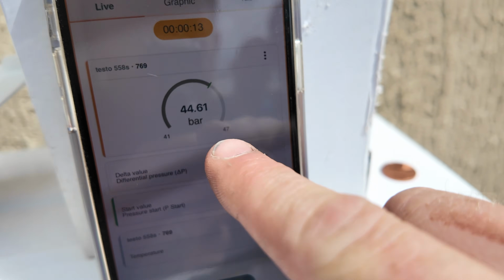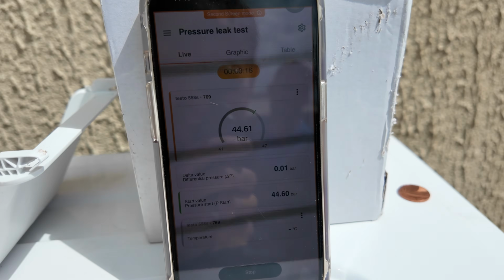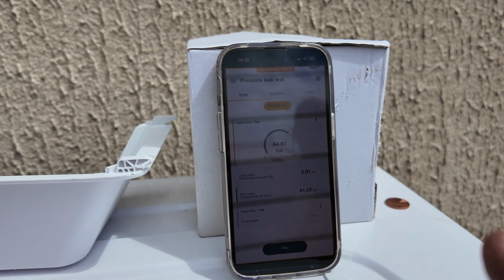You can see the time is starting now, we're on 44.61, so we'll check that in a bit to make sure it passes the pressure test. It's a good time to start doing your indoor finishing off. You want to get your pressure test on as soon as you can, so get your pipe work in and get your pressure test running, because that's what takes the longest amount of time. So what we can do now is all the wiring, all the cosmetic stuff, because we've got time to kill while we leave that to do the pressure test.